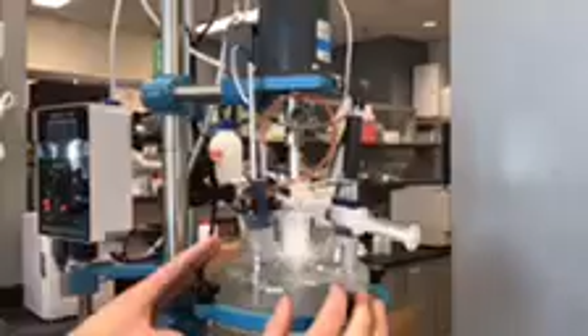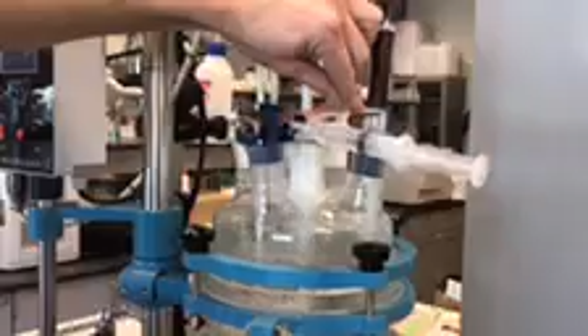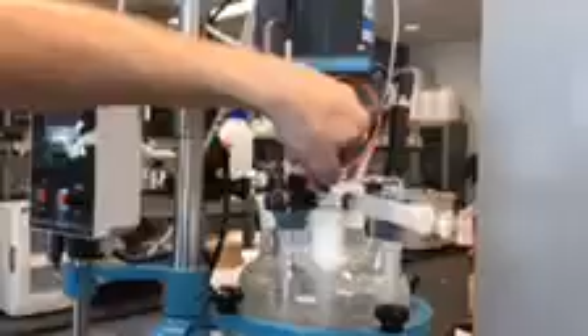Furthermore, if we want to pull a sample and inject it in here, again without disrupting the gases inside, you simply connect this back up, open this valve, open the bypass valve, and simply press it in, and you'll see it spill right off into there. Now you close this, and it's still a sealed system.